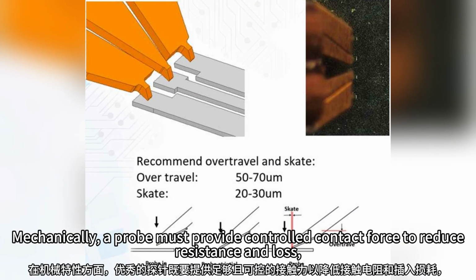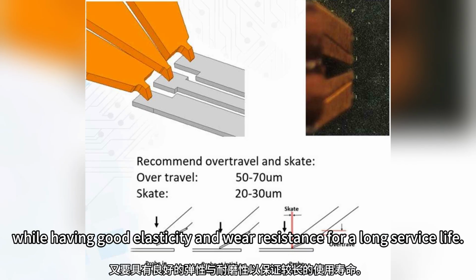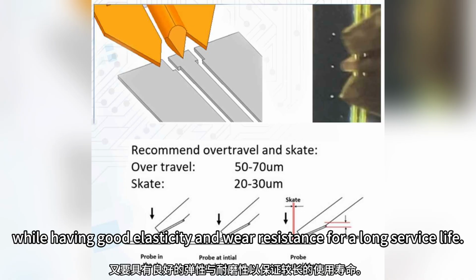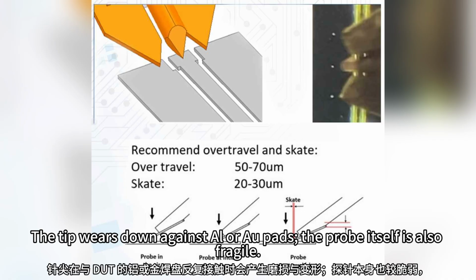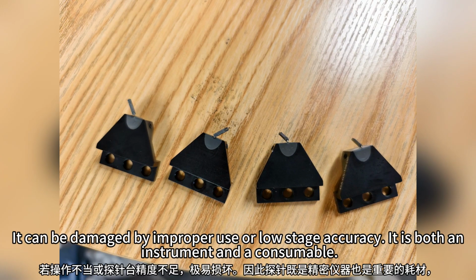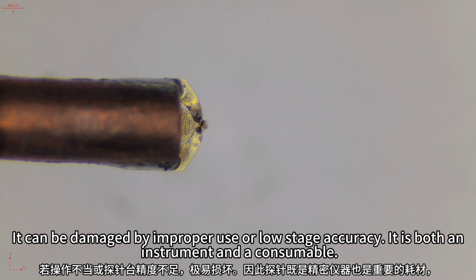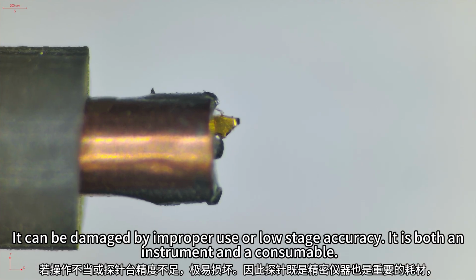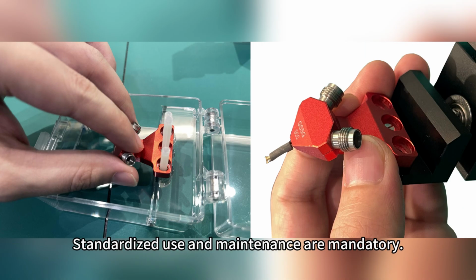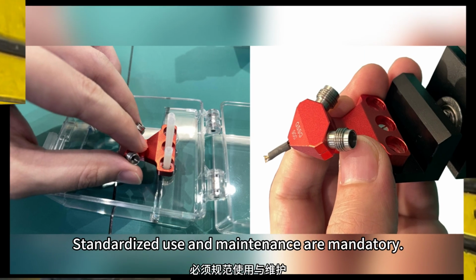Mechanically, a probe must provide controlled contact force to reduce resistance and loss, while having good elasticity and wear resistance for a long service life. The tip wears down against aluminum pads. The probe itself is also fragile. It can be damaged by improper use or low stage accuracy. It is both an instrument and a consumable. Standardized use and maintenance are mandatory.